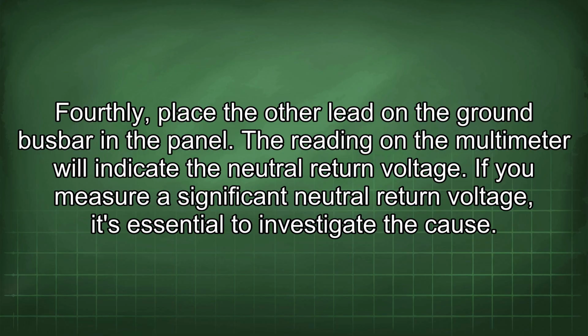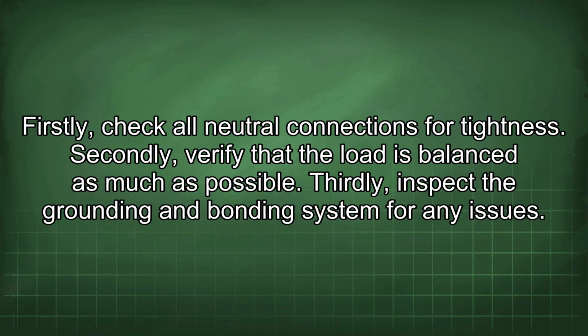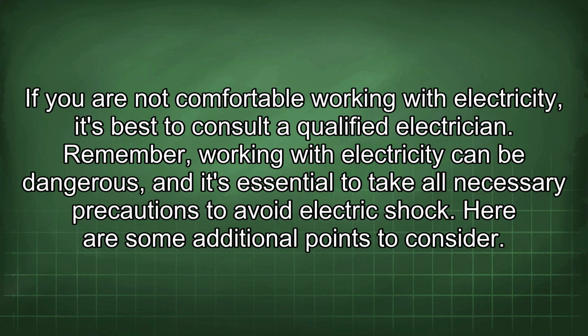If you measure a significant neutral return voltage, it's essential to investigate the cause. Firstly, check all neutral connections for tightness. Secondly, verify that the load is balanced as much as possible. Thirdly, inspect the grounding and bonding system for any issues. If you are not comfortable working with electricity, it's best to consult a qualified electrician. Remember, working with electricity can be dangerous, and it's essential to take all necessary precautions to avoid electric shock.